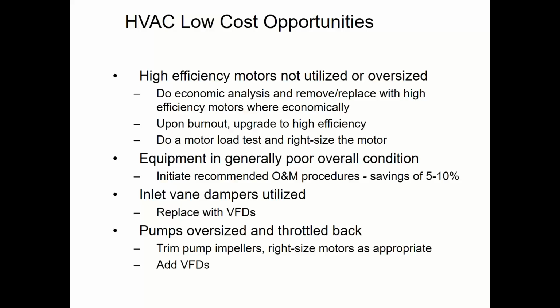In terms of actual projects, which I'm assuming is what Mike really wants to know, I have no idea. You'd have to look at the cost of labor in your area to figure out how much it's going to actually cost to clean the coil, and then after that you could calculate the paybacks. But if nothing else, on the indoor evaporator coil, just because you don't want gross stuff floating into the airstream, that alone should be enough reason to clean it, even if there was no energy savings. Energy savings is kind of a bonus on the indoor coil.